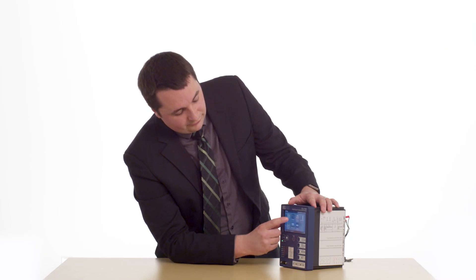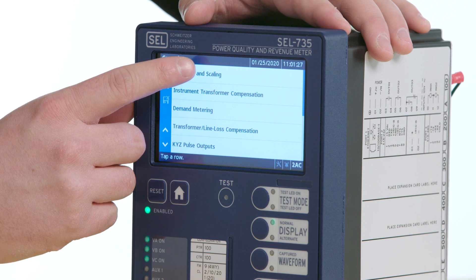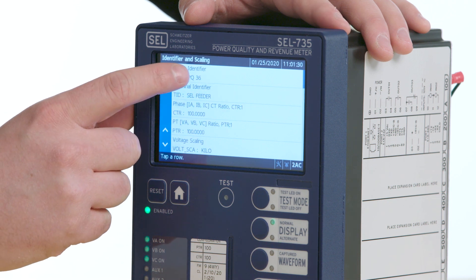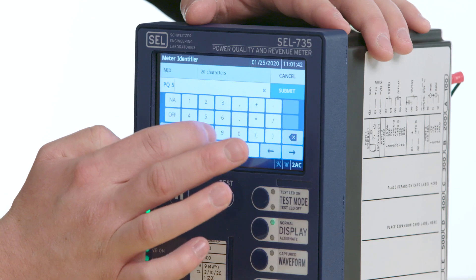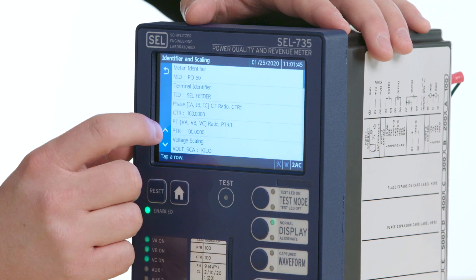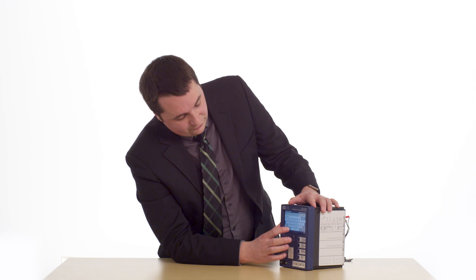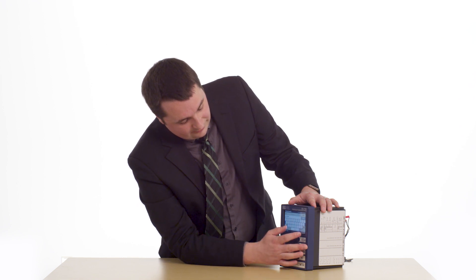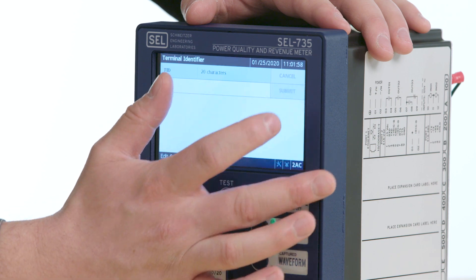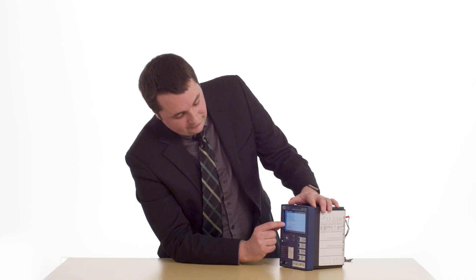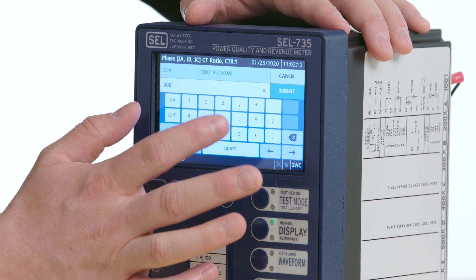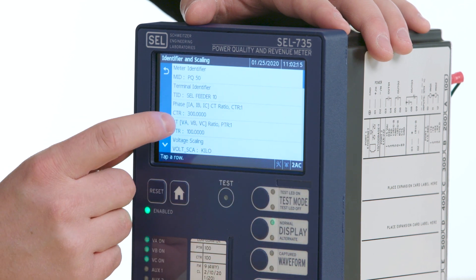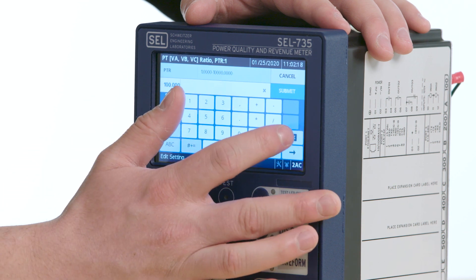Lastly, I will go into the general settings and change the basic settings for this setup. The first thing I'll do is change the meter identifier — in this case, this is Power Quality Meter number 50. Next, I will change the terminal identification, which is SEL Feeder number 10. The next step is to change the CT ratio and the PT ratio. We are using a CT ratio of 300 and a PT ratio of 100.